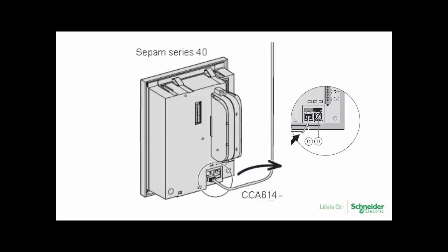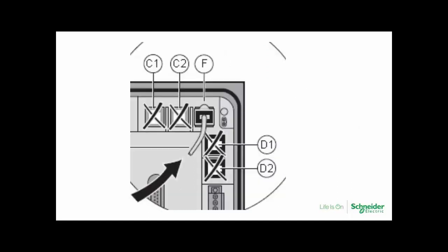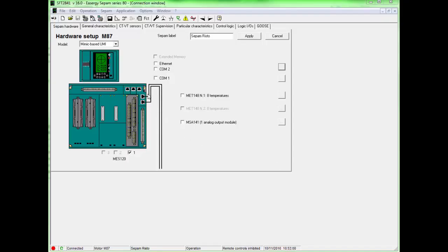In Sepam 40, connect the CCA614 cable to port C. In Sepam 80, connect the CCA614 cable to port F. IP address is set with SFT2841.